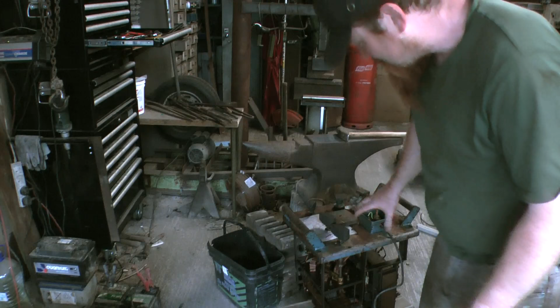First I'm going to turn on the generator and switch the workshop over to generator power, simply because the generator is cheaper than the inverter, so if I'm going to blow something up, it should be that. I expect the inrush current for this welder will probably pop the fuse before anything else happens.